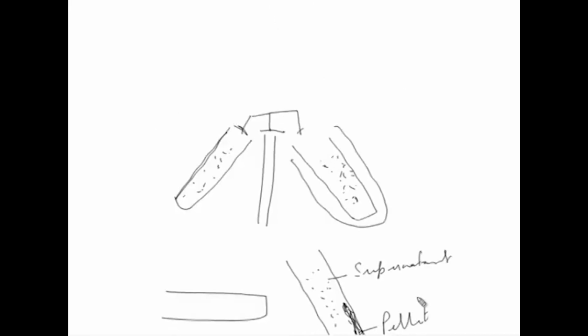Now, remember, depending on the kind of rotor, for an angle rotor, this is an angle rotor, the pellet will settle down at this side. If it is a swinging bucket rotor, where the tubes are free and not constrained, when the centrifuge is switched on, they will swing outward. In the angle rotor the tube is constrained in the slot, but these are open.